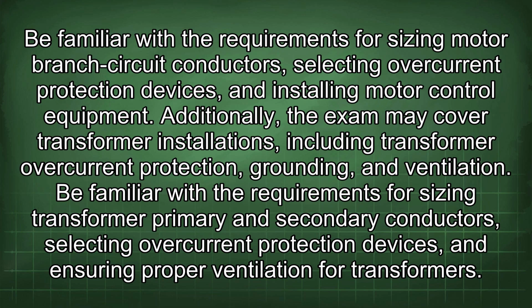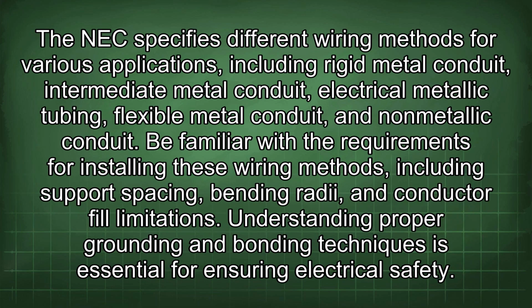for transformers. The NEC specifies different wiring methods for various applications, including rigid metal conduit, intermediate metal conduit, electrical metallic tubing, flexible metal conduit, and non-metallic conduit. Be familiar with the requirements for installing these wiring methods, including support spacing, bending radii, and conductor fill limitations.